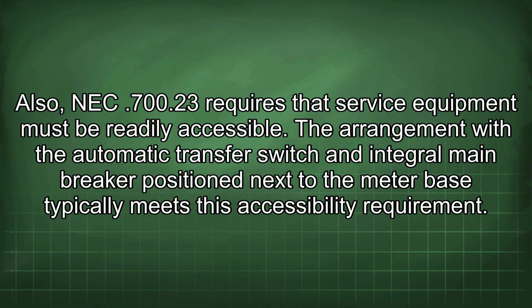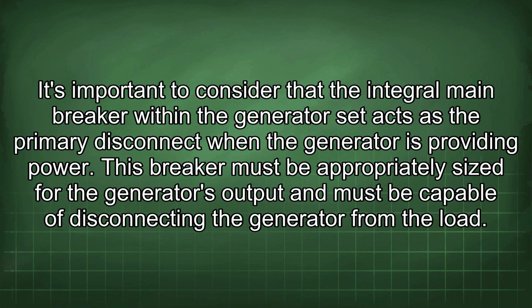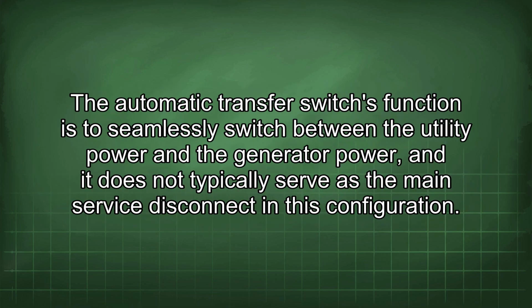The arrangement with the automatic transfer switch and integral main breaker positioned next to the meter base typically meets this accessibility requirement. It's important to consider that the integral main breaker within the generator set acts as the primary disconnect when the generator is providing power. This breaker must be appropriately sized for the generator's output and must be capable of disconnecting the generator from the load. The automatic transfer switch's function is to seamlessly switch between the utility power and the generator power, and it does not typically serve as the main service disconnect in this configuration.